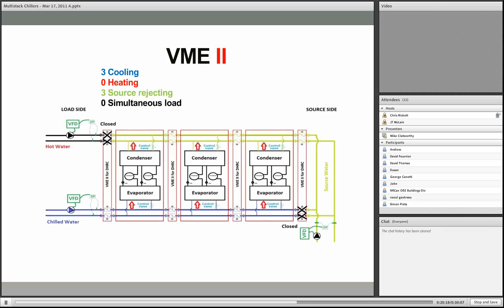Now, by eliminating reversing valves, I've eliminated lifting twice or using compressors twice. So I'm taking heat out of the heating load or out of the chilled water and putting it into the heating load directly without lifting it, without using the refrigeration process twice. And that is the weakness of most heat pump systems. So VME2 allows a single lift. It allows the elimination of reversing valves, and it allows taking advantage of that efficiency gain.